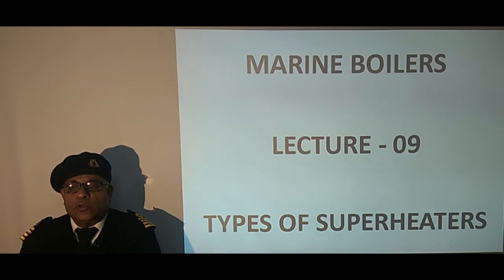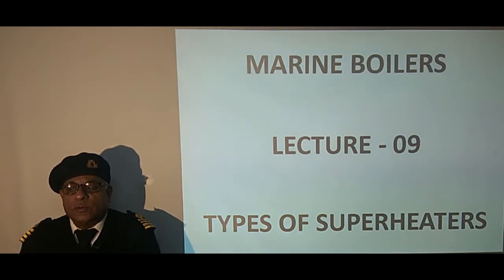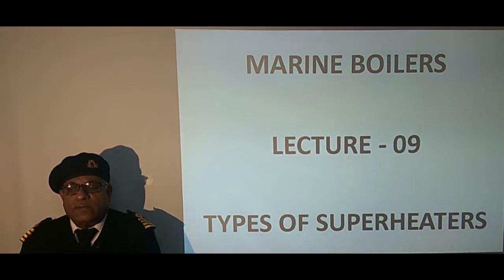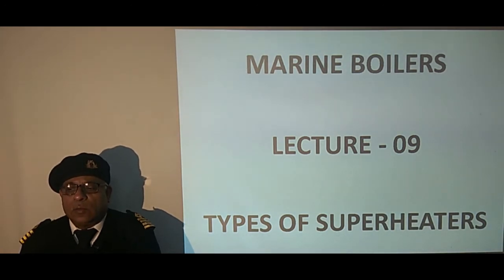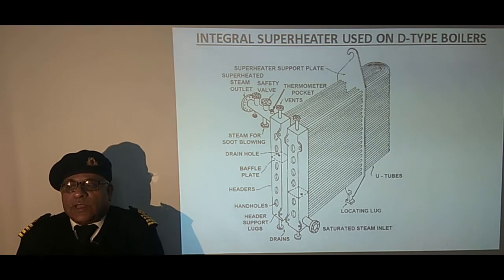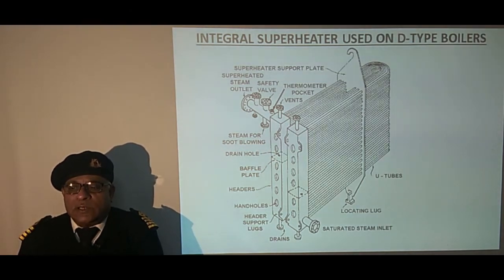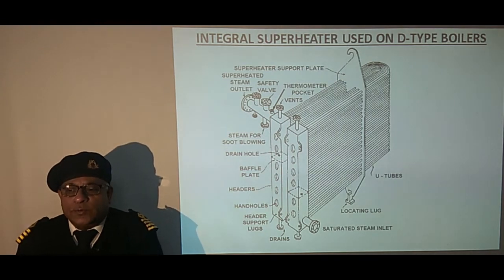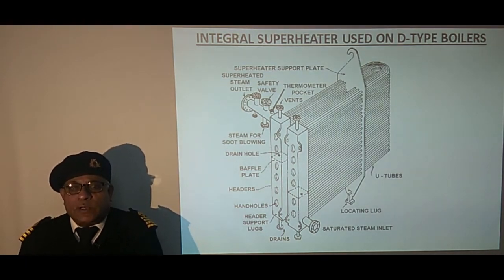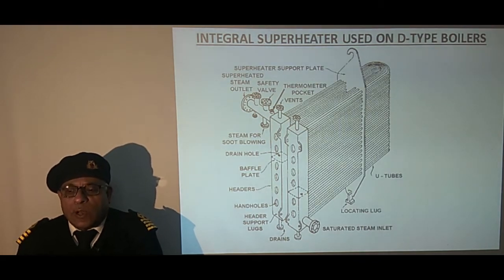Integral superheaters are close to the furnace and sandwiched between generating tubes. On the other hand, external superheaters are fitted on the exhaust side and are well protected against overheating. This sketch shows an integral superheater used on D type boilers, placed between generating tubes and secured with superheater support plate and header support lugs.